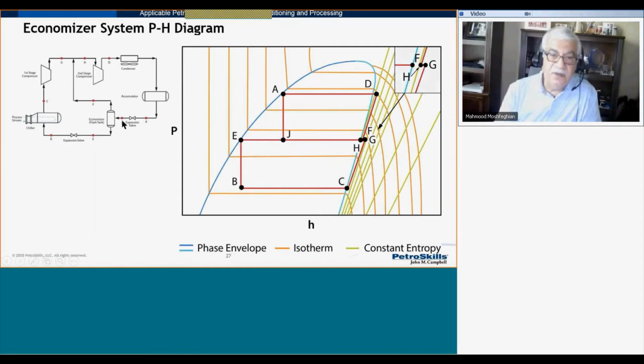So intermediate pressure sets the pressure at the outlet of my first expansion valve. So I start at point A, which is saturated liquid, I go all the way down to interstage pressure in this valve here, and then go to the separator, the liquid, which is point E, going to the second expansion valve, and dropping the pressure from interstage pressure to the chiller pressure, which is point B before entering the chiller. In the chiller, I go from point B to C, and then I go to compression of first stage from C to G.